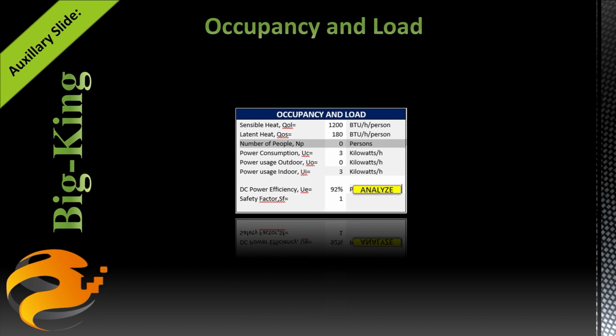Power usage outdoor pertains to any outdoor units that reside outside the building. This is subtracted from the building envelope heat calculation, resulting in the power usage indoor, which is determined to be the total heat load that needs to be removed from the building. DC power efficiency is applied to the DC power usage on HVAC units, which include DC-powered components, and should account for inverter and rectifier combined efficiency. The safety factor is typically set to 1, but can quickly be adjusted to meet engineering requirements.